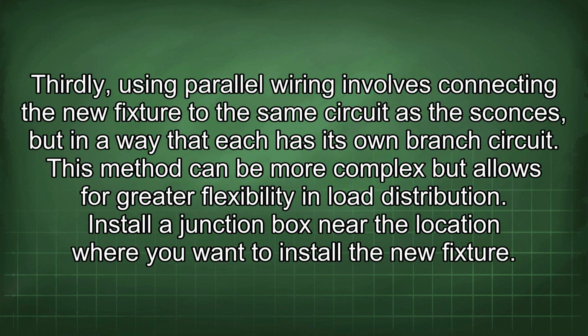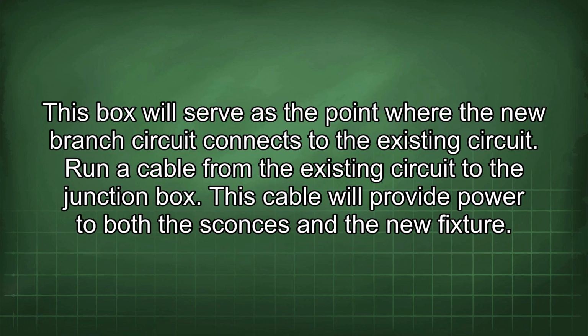Thirdly, using parallel wiring involves connecting the new fixture to the same circuit as the sconces, but in a way that each has its own branch circuit. This method can be more complex but allows for greater flexibility in load distribution. Install a junction box near the location where you want to install the new fixture. This box will serve as the point where the new branch circuit connects to the existing circuit.